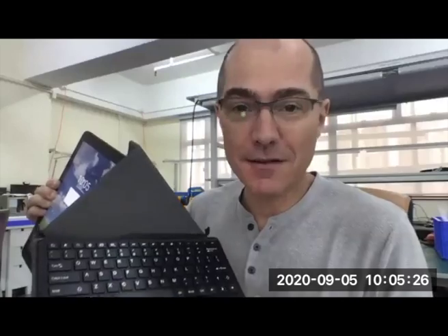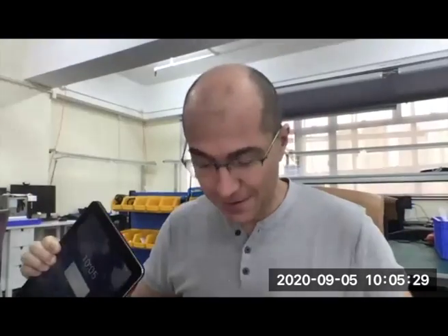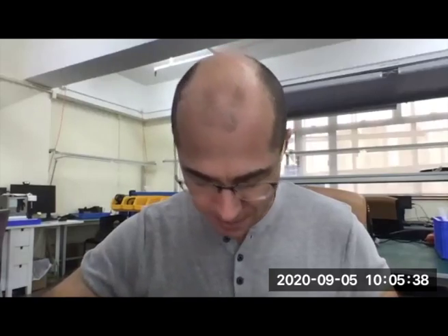And that beeping sound is a machine having failed the high pot insulation test. Every single machine has to have that test. We test it twice, actually, before we do any burn-in, and then after all the burn-in calibration, we test it again. That can be, forget it, 20,000 volts or something insane. Essentially, if there's any insulation that's not all the way where it should be, it'll leak, and that's a fail.